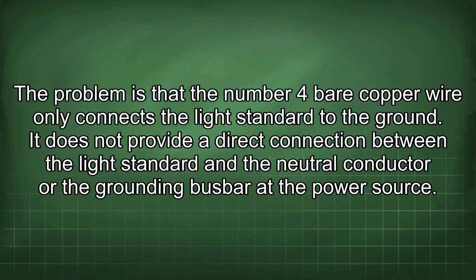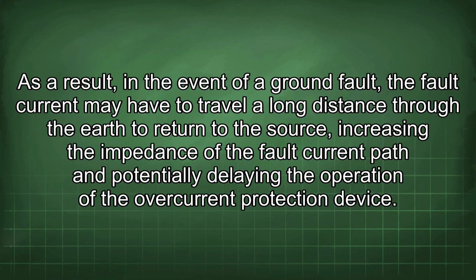It does not provide a direct connection between the light standard and the neutral conductor or the grounding busbar at the power source. As a result, in the event of a ground fault, the fault current may have to travel a long distance through the earth to return to the source, increasing the impedance of the fault current path and potentially delaying the operation of the overcurrent protection device.